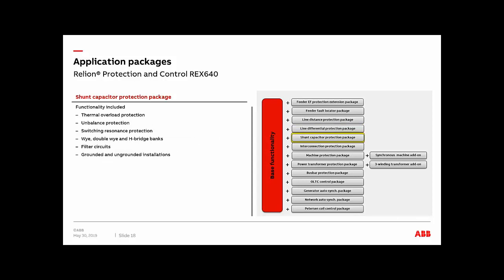When it comes to the shunt capacitor protection package, on this one we're going to have thermal overload protection, and this is going to be based on the peak value of the integrated current, which is going to be proportional to the voltage across the capacitor. It's going to be our thermal calculation. Then we're going to have unbalance protection. In the unbalance protection, we're going to protect double Y or H bridge capacitor connected banks.